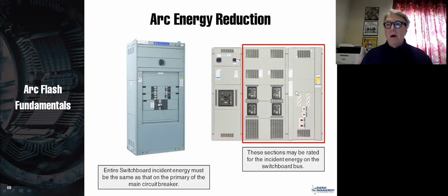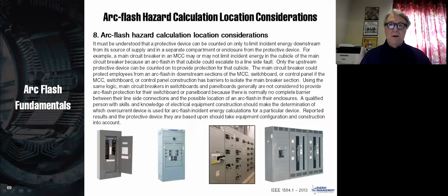of calories. On the other hand, if you have a situation like this in which you have multiple vertical sections and they are isolated by a metallic barrier between them, then this section can have a calorie rating based on the calories coming into the gear. The rest of your gear can have a calorie rating based upon the secondary side of that main breaker. How do we know that that's possible? Because it's right here in 1584, and I'm not going to read that all, but 1584 says that basically what I explained to you is very much kosher, and we can do that.